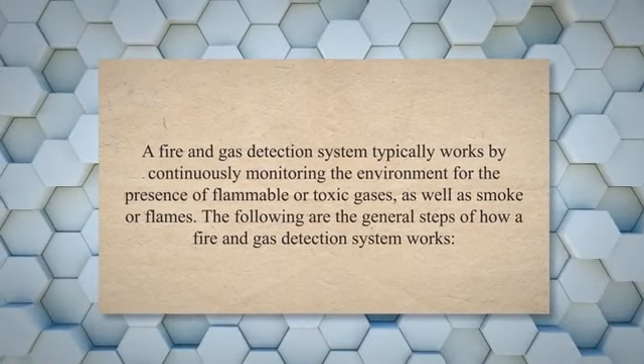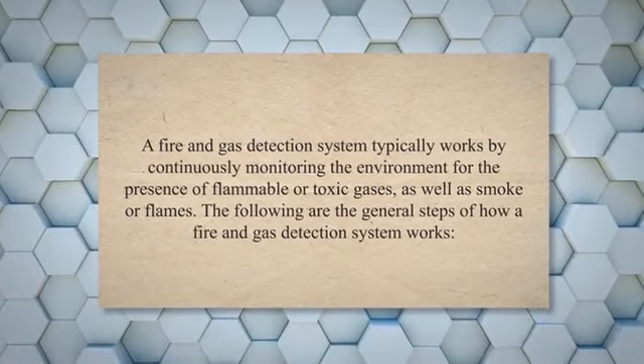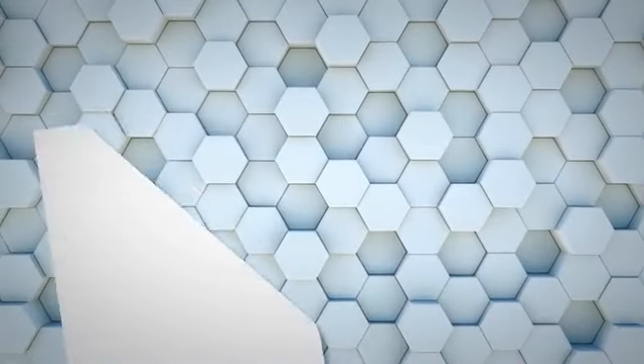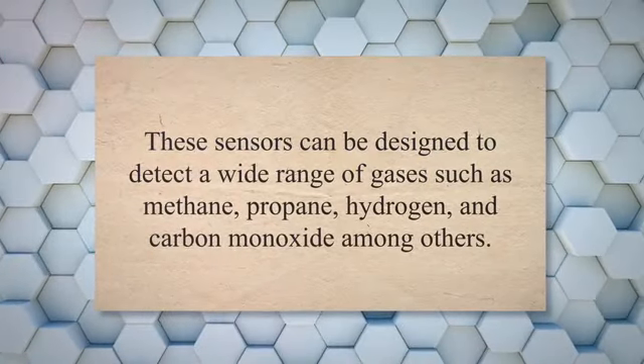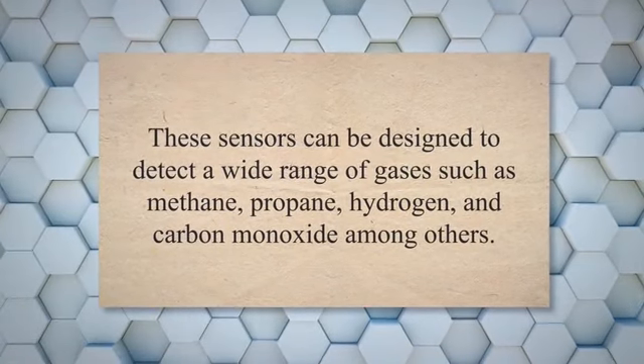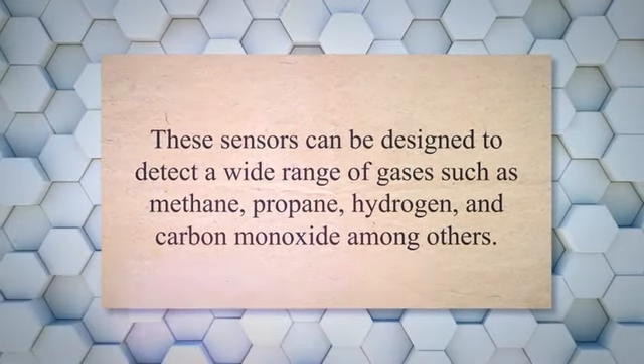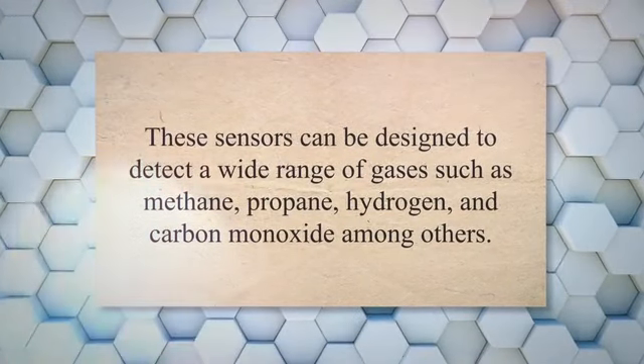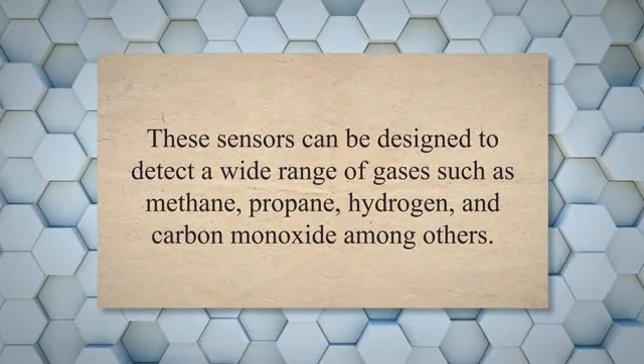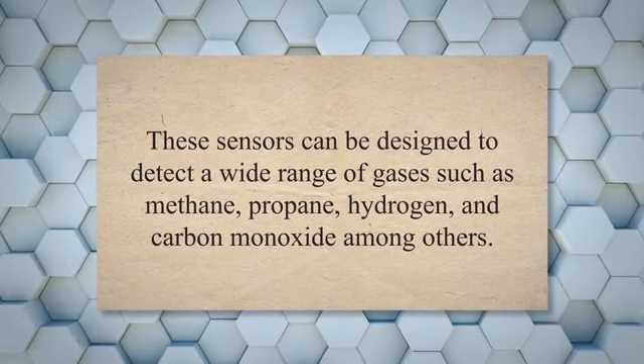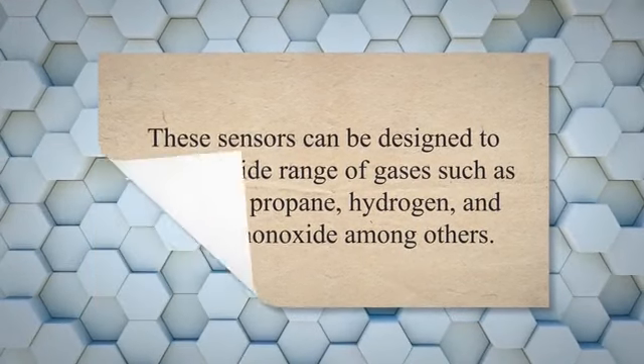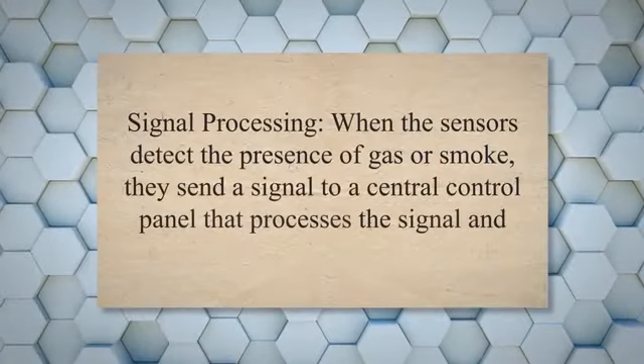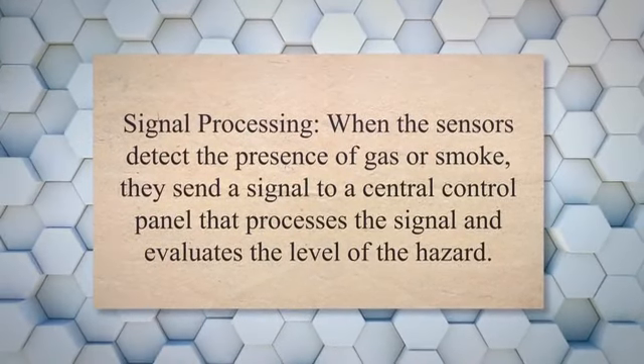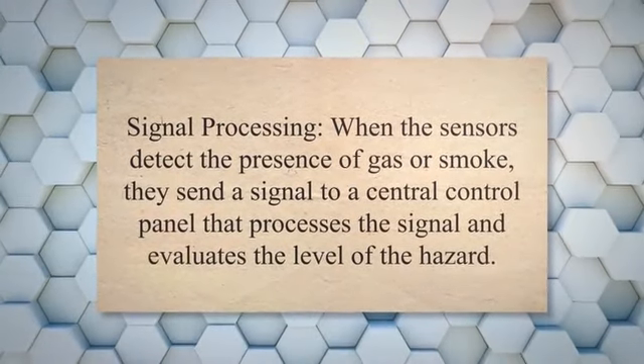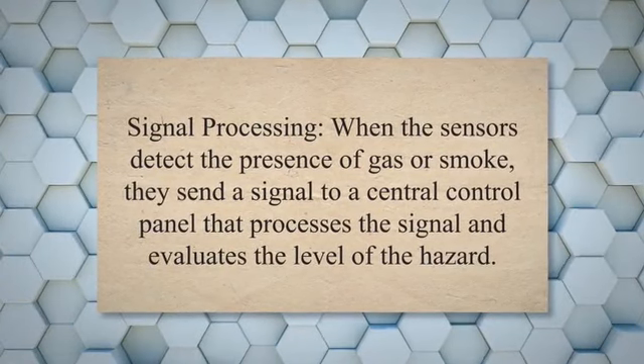The following are the general steps of how a fire and gas detection system works. Gas and smoke detection. The system uses a network of sensors and detectors to detect the presence of gas or smoke. These sensors can be designed to detect a wide range of gases such as methane, propane, hydrogen, and carbon monoxide, among others. Signal processing. When the sensors detect the presence of gas or smoke, they send a signal to a central control panel that processes the signal and evaluates the level of the hazard.